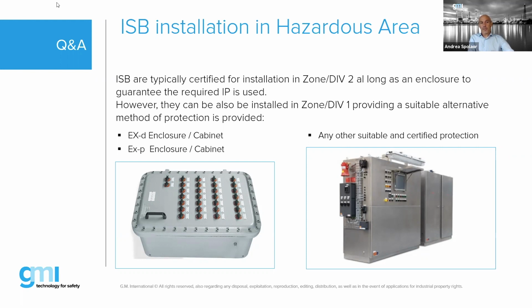Also, other instruments can be certified for hazardous area installation. Okay. In case it's not certified, the unit or any electronic device that is not certified for hazardous area must be included in an Ex d, Ex p enclosure, or any other suitable certified protection. So, just to recap, if the product is not suitable for hazardous area installation, it can be installed in the hazardous area if, let's say, it is included in this kind of protected box.